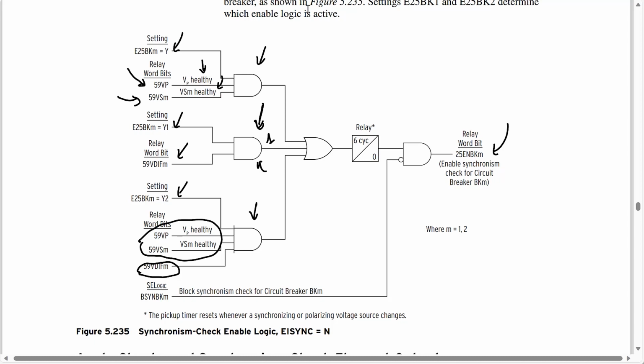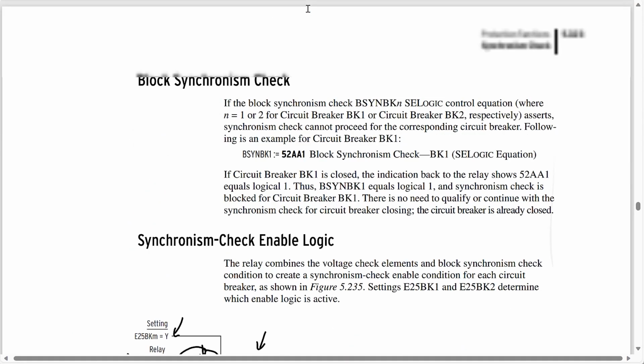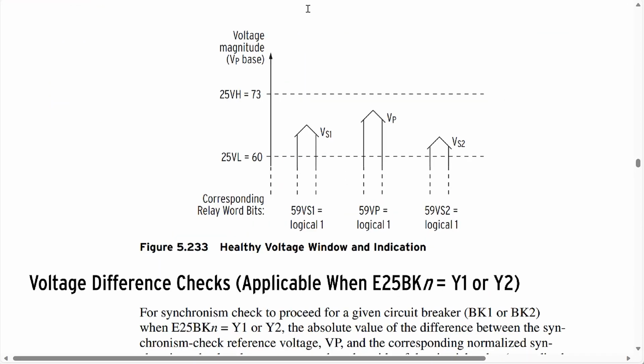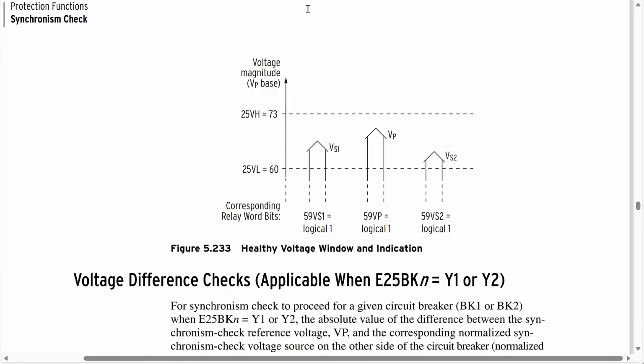Now, I mentioned before that here on the top, we see healthy voltage for VP and VS1, but what does that actually mean? What's the range that we would consider healthy? To see that, let's go to page 484. So that's shown over here in this graph. So again, what we define as healthy voltage is a band that we set within the settings file, and we usually set that around the nominal voltage. For our case, we're going to set that to be plus or minus 10% of the nominal voltage.